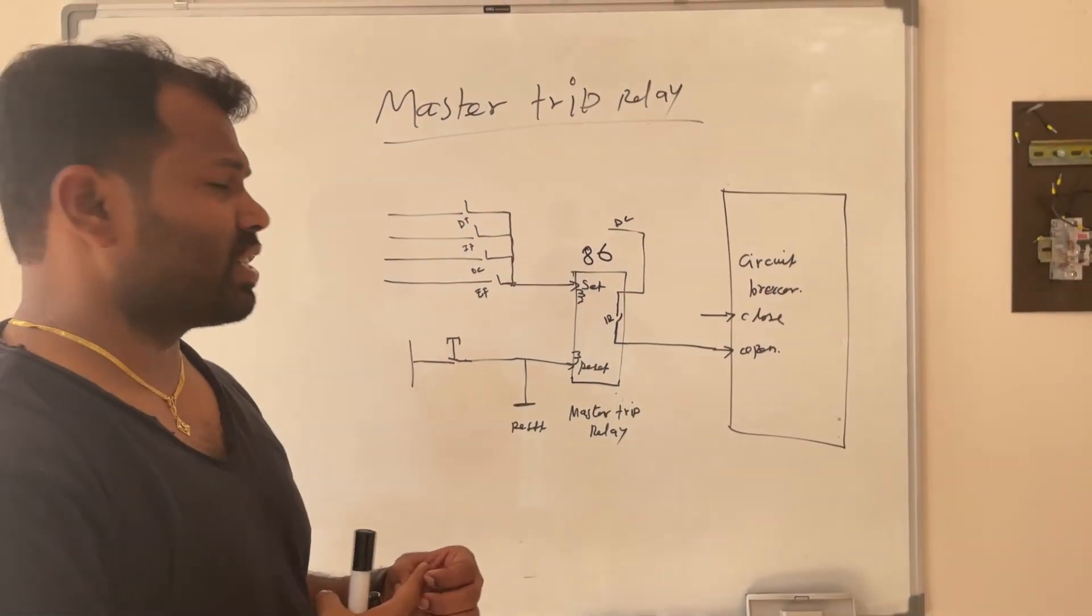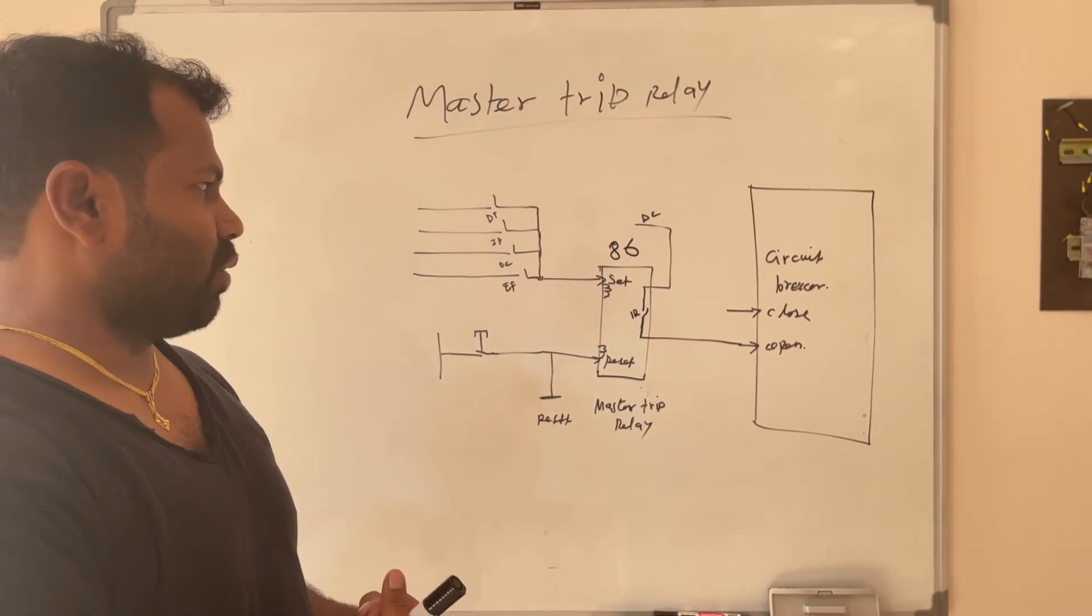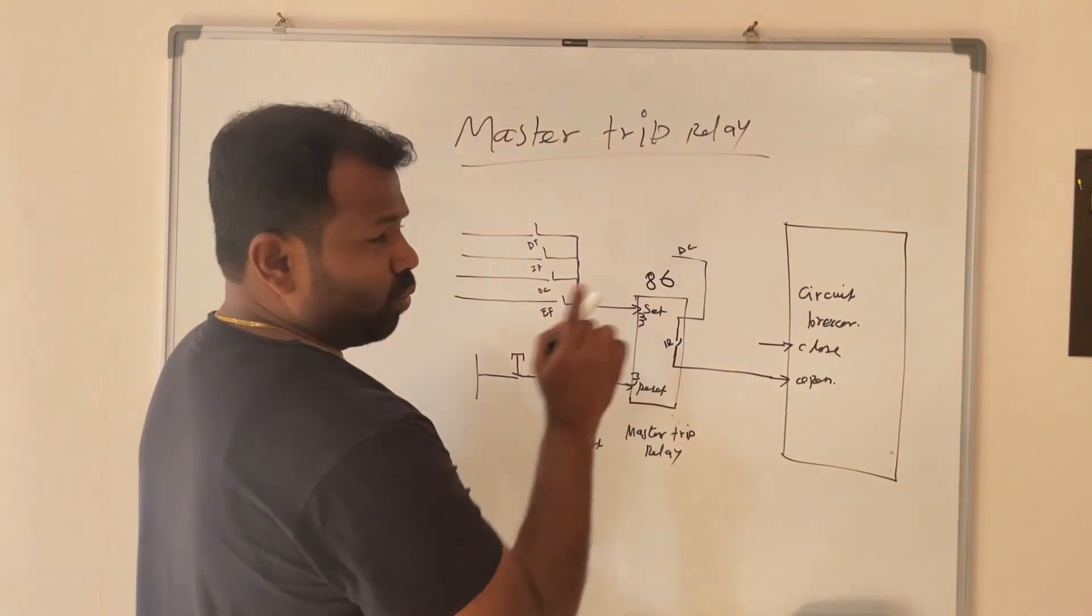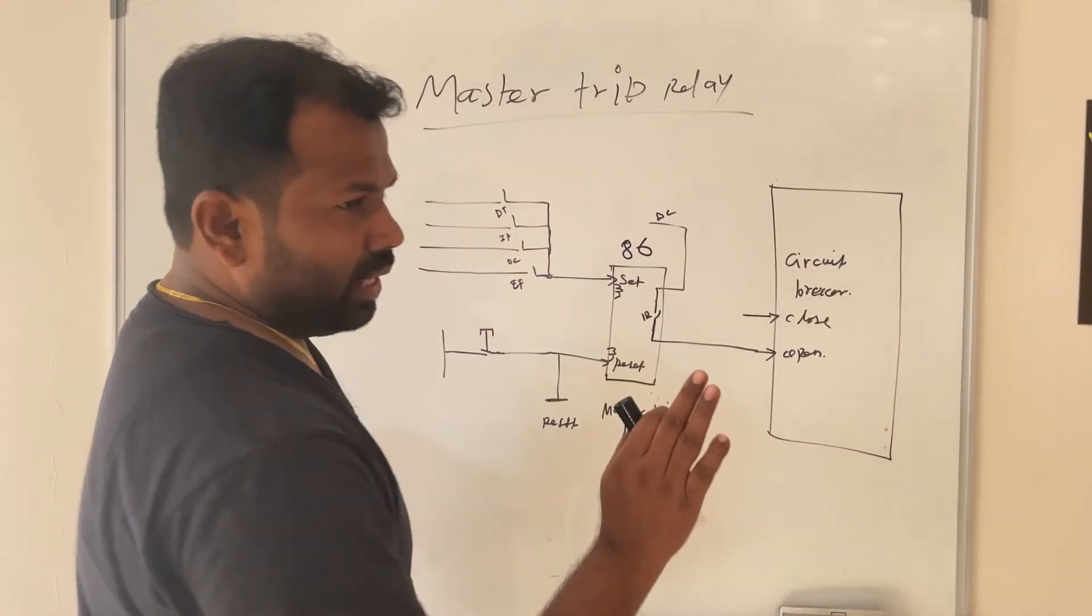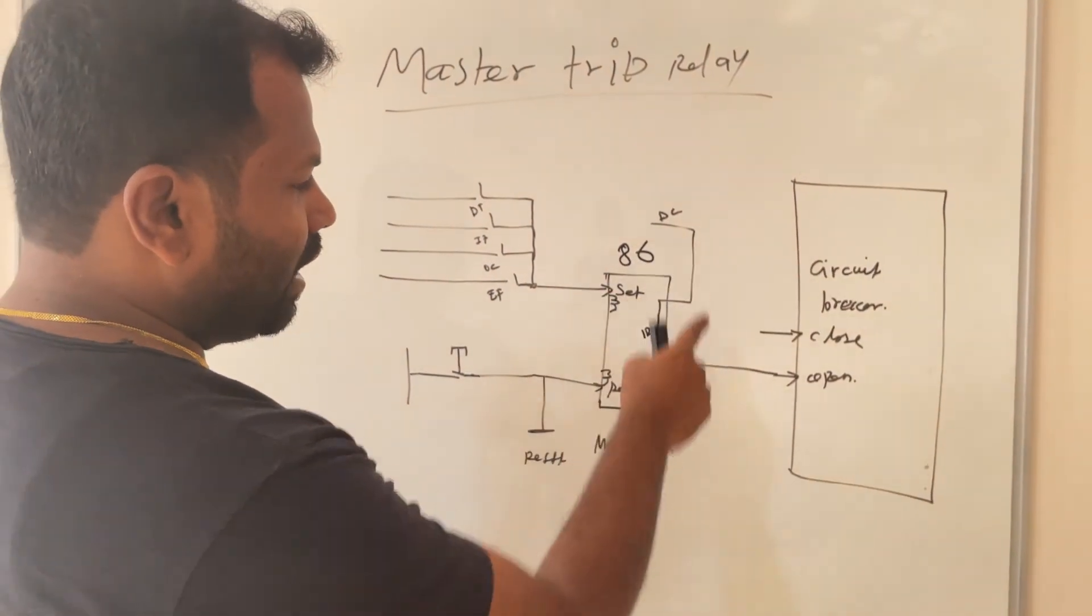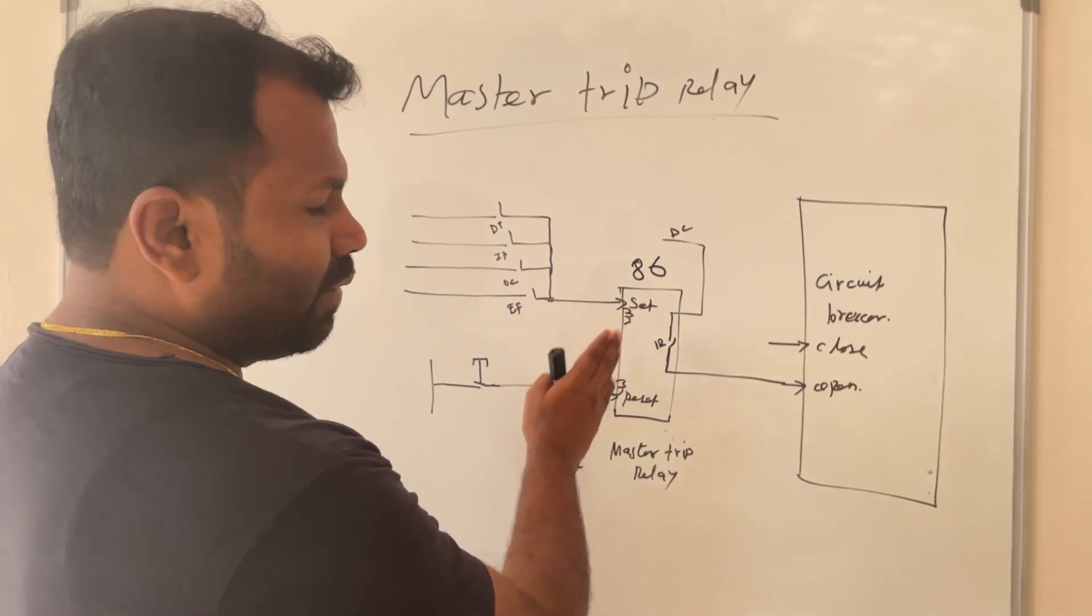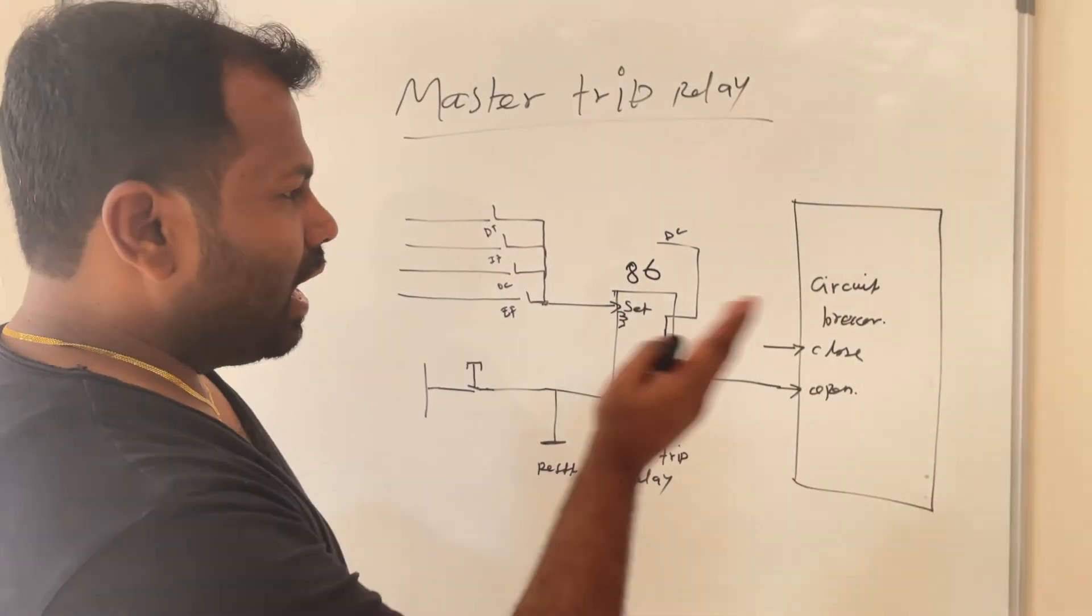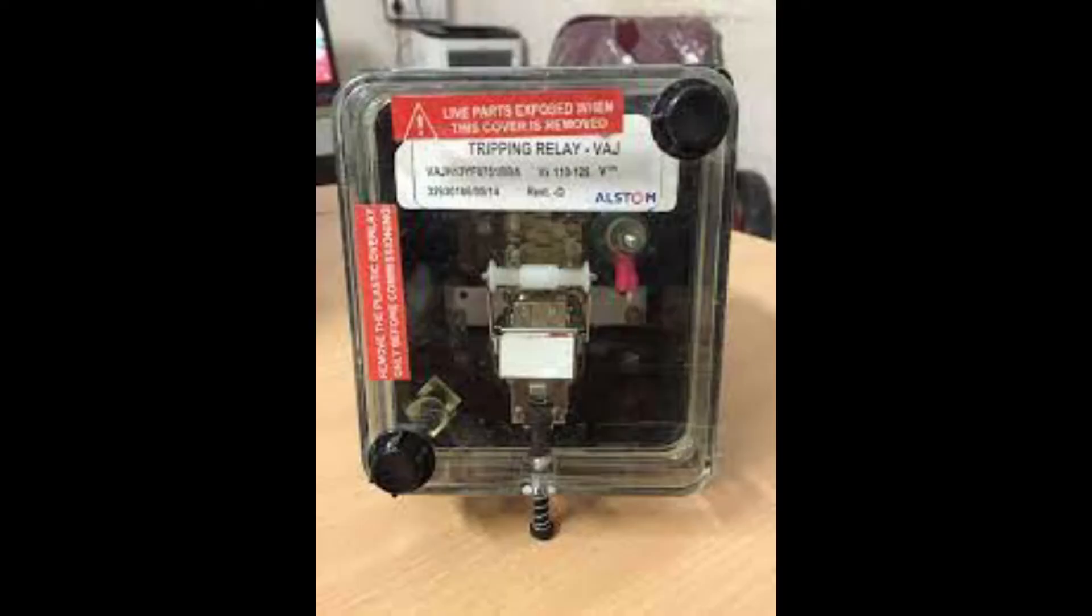In industrial receiving stations and also power generation stations. One more important thing is this master trip relay is not sensing any trip directly. This will not sense or monitor any protection. This will receive external signal and it will react based on the signal only. This master trip relay has another name called lockout relay.